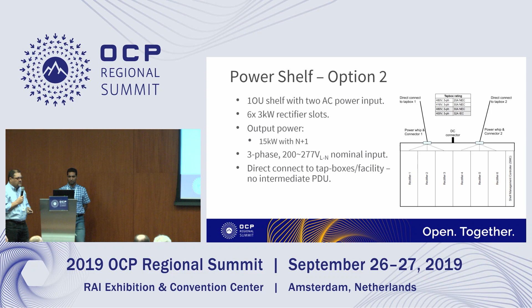If we go on to the second option, it's a 2-corded system, but it's still considered N+1. We're going down in cord ampacity to get to this type of power per rack. Same application results, 15 kilowatts N+1, no PDU, no breakers in the rack, direct connection to the overhead or underfloor.